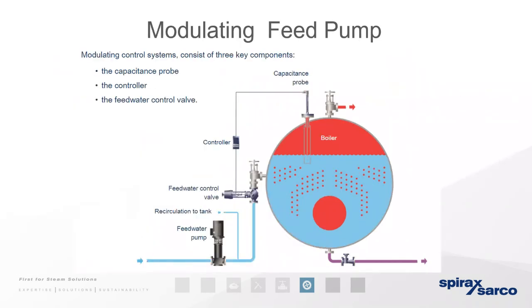So modulating, as we were just talking here, as you can see, it's a typical setup. So you've got a capacitance probe, which is telling you the level. It will be set at a certain point. You've got your feed water control and your controller here and a feed water pump, so a modulating pump. You also have a recirc, so when this closes, you don't deadhead the pump. So you want a small orifice pipe, so something that's maybe 1/4 inch, 1/2 inch, feeding back upstream, so that when this pump is stopping or slowing down, there is a pressure release there, so you don't damage the pump. This is capacitance only as well.